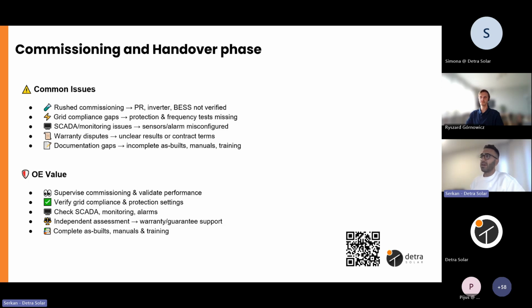Grid compliance gaps are also quite frequent, like protection settings or reactive power tests may be missing. SCADA systems and sensors may not be properly calibrated, and alarms may be misconfigured. These gaps can lead to disputes over warranties or performance guarantees if the system doesn't deliver as promised.